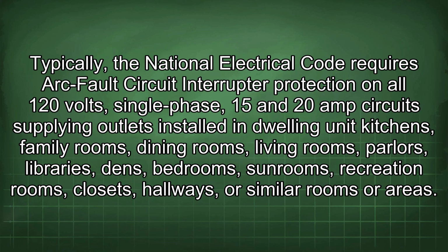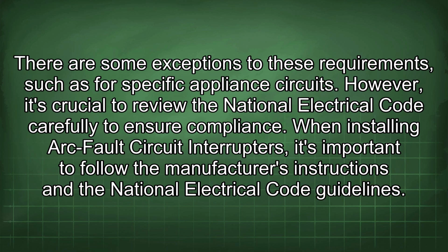Typically, the National Electrical Code requires arc fault circuit interrupter protection on all 120 volt, single-phase, 15 and 20 amp circuits supplying outlets installed in dwelling unit kitchens, family rooms, dining rooms, living rooms, parlors, libraries, dens, bedrooms, sunrooms, recreation rooms, closets, hallways, or similar rooms or areas. There are some exceptions to these requirements, such as for specific appliance circuits. However, it's crucial to review the National Electrical Code carefully to ensure compliance.